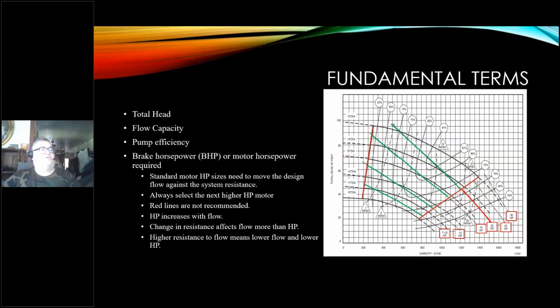Now, we also work on this to lower our horsepower. These are standard motor horsepowers. They're always selected as the next higher horsepower motor. So if you're over the line on one, you select the next line up. The red lines are not recommended. The horsepower increases with flow. That just makes sense. You move more water, you use more horsepower. However, changing resistance affects the flow more than the horsepower. So the resistance to flow will actually drop your horsepower. It resists the flow of water, and the horsepower will actually drop. Horsepower increases with flow, and it decreases with a decrease in flow. Changing resistance affects flow more than horsepower, and the higher resistance to flow means a lower flow and a lower horsepower. And we'll talk about that in a few more slides where you actually see what's going on.